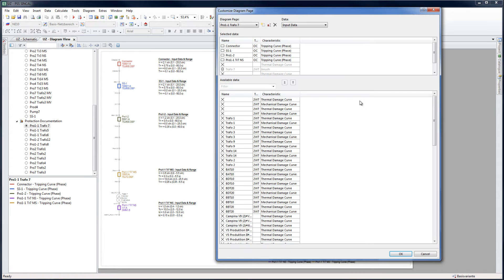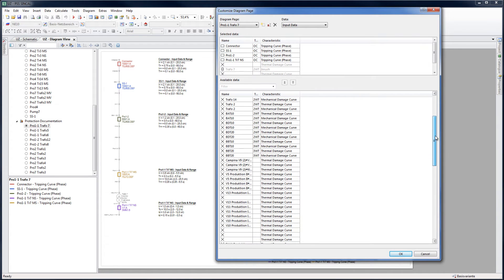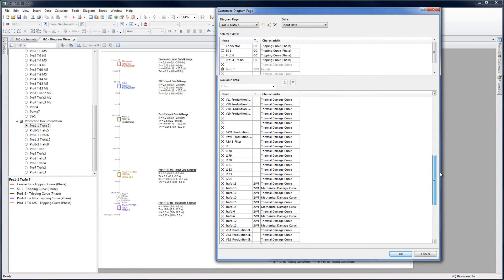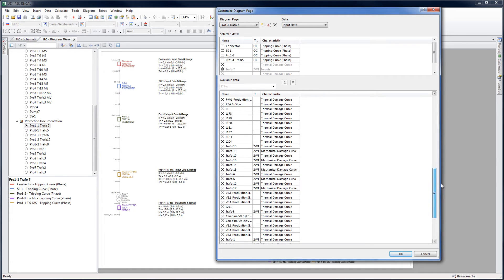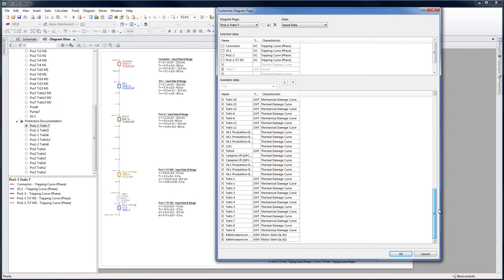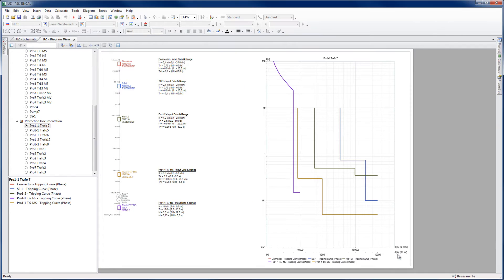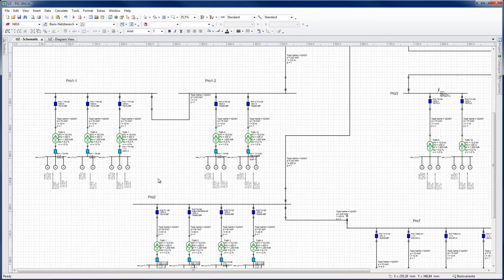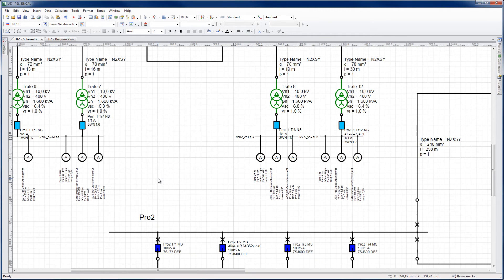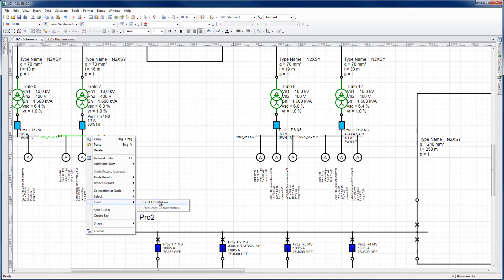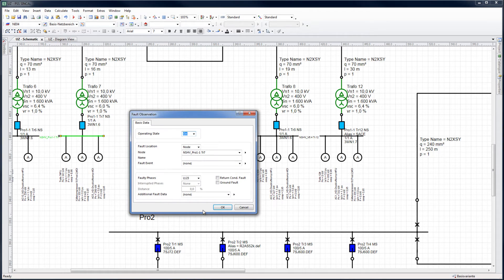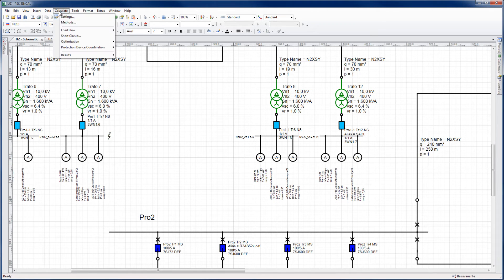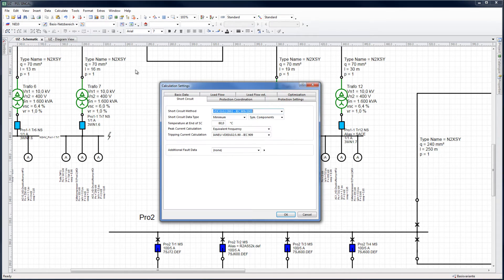Further characteristic curves can also be displayed, for example, thermal damage curves, motor start-up or short circuit characteristics. The range of possible short circuits can also be generated by PSS SINCAL in the simulation mode. Insert a fault simulation at this bus bar. Now, perform a maximum three-phase and a minimum two-phase short circuit.